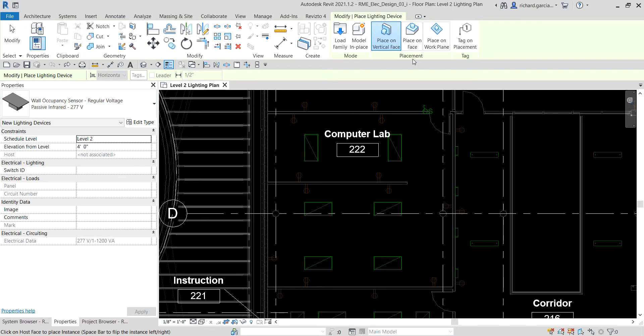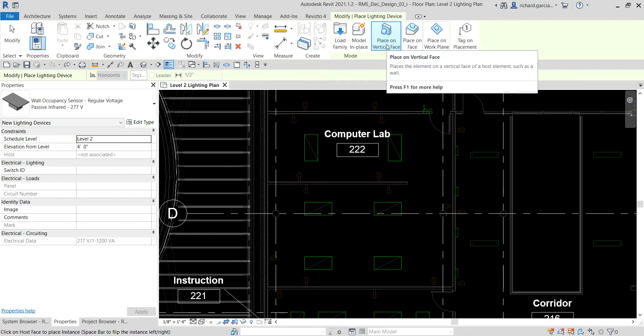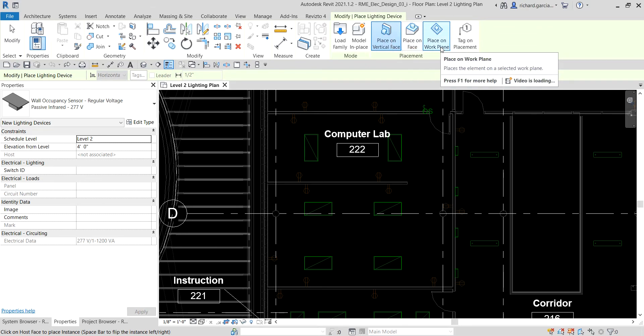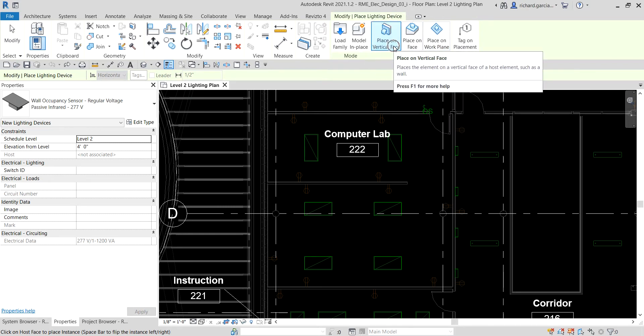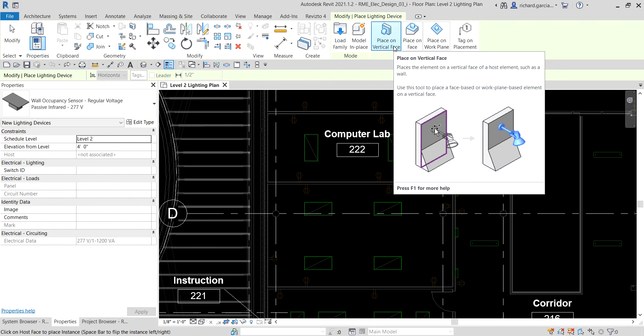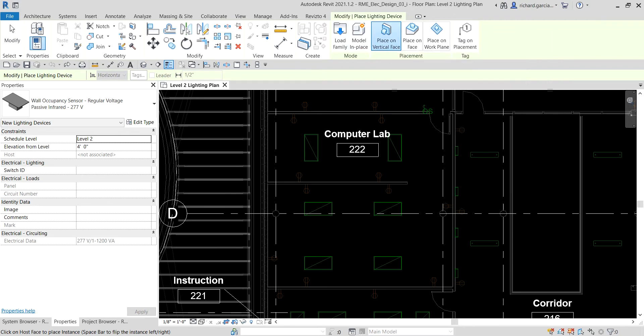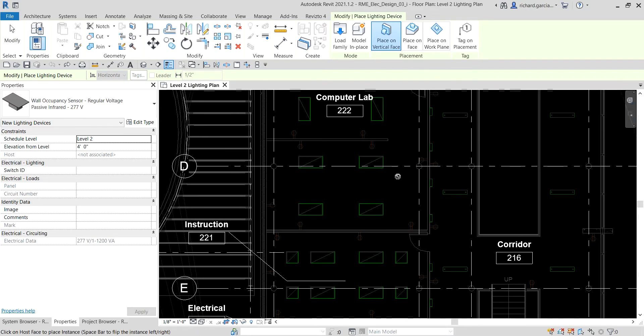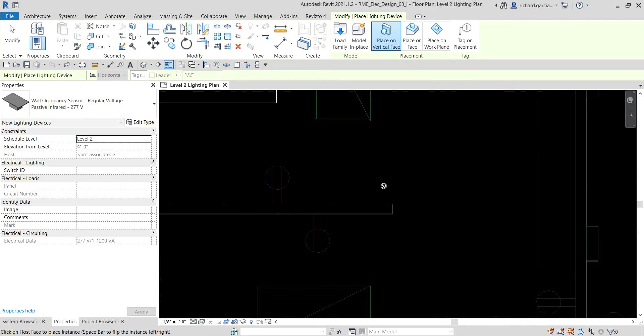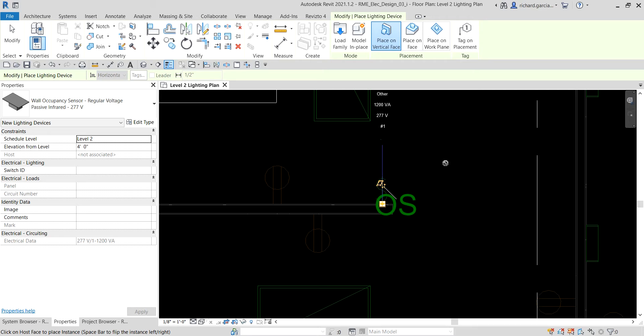Before you place it, there's a placement panel with options: you can place on vertical face, place on face, or place on work plane. Since we're placing it on the wall, make sure 'Place on Vertical Face' is selected — it places the element on a vertical face of a host element such as a wall. Now let's place it. If you move your pointer away from the wall, it will say 'Cannot' — you cannot place a lighting device away from a vertical face.